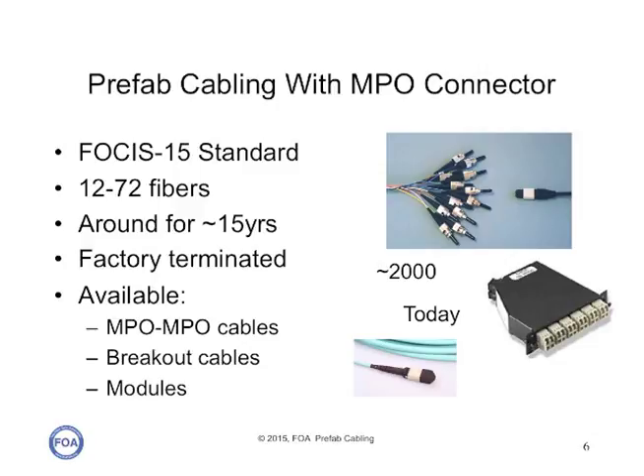Many prefab cabling systems use what we call an MPO connector, multi-position optical connector, which is a connector that has anywhere from 12 to 72 fibers in a single connector. This connector's been around for 15 years. It's strictly factory terminated, although there are options to field terminate with pre-polished splice connectors or fusion splicing on pigtails. In today's market, you'll see MPO to MPO cables, breakout cables, and modules, which are terminated in the MPO on one side and single fiber connectors on the other.